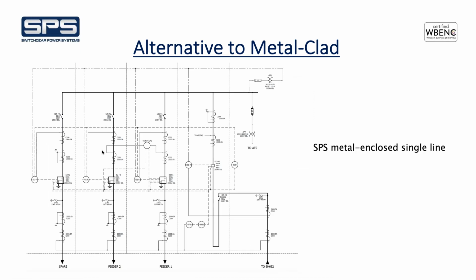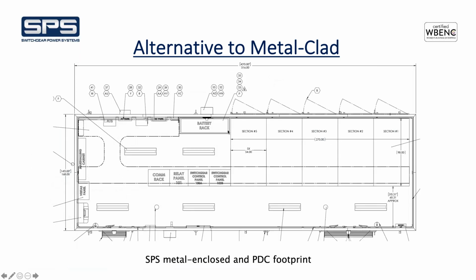So this is the metal enclosed single line that we proposed to them as an alternative. It included an incoming main switch at 2000 amps, and then your main circuit breaker, 2000 amps, and then 3 feeder breakers, one of which was a spare. Each feeder breaker had a 600 amp switch incorporated with it. In this case, they were load break because of the amperage. The main switch was a non-load break switch. So we gave them the visible break, and the footprint that we came up with.